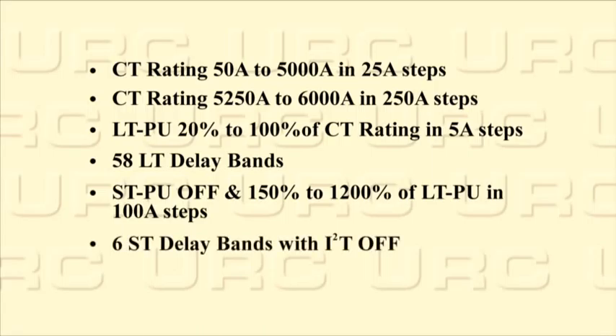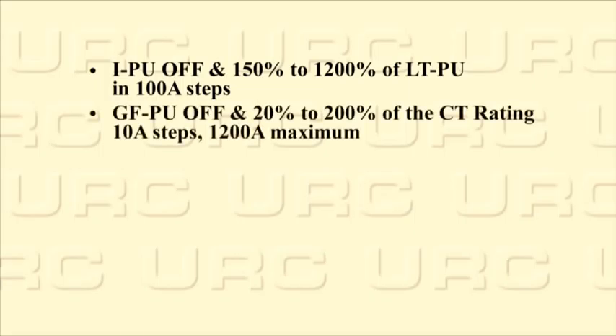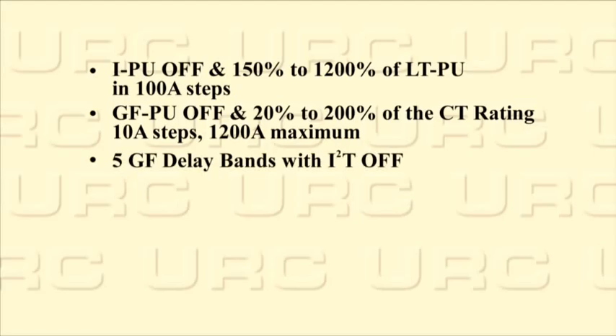There are 6 short time delay bands with I2T off, and 6 short time delay bands with I2T on. The instantaneous pickup can be set from 150% to 1200% of the long time pickup setting in 100 amp steps. An off setting is available as long as short time is not set to off. The ground fault pickup can be set from 20% to 200% of the CT rating in 10 amp steps with a maximum of 1200 amps. If ground fault is not required, an off setting is available. There are 5 ground fault delay bands with I2T off and 5 ground fault delay bands with I2T on.